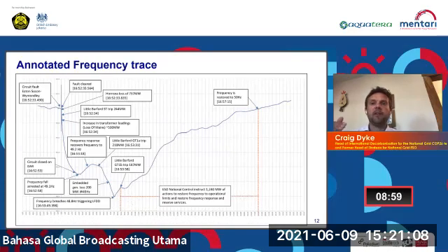Then that starts to arrest the frequency, which then drives back up. Again, as the frequency starts to return, we then see the final gas turbine trip at Little Barford, so there's a little bit of a dip in frequency before we see the trace start to restore and work its way back up through the automatic frequency control, but also the actions the control room took, using typical gas turbines, interconnection, hydro, and also storage through batteries. And at 1657 is where we saw the frequency restored back up to 50 hertz.